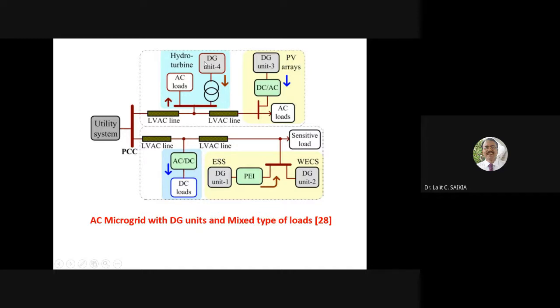Now one DG unit, say a hydro turbine—small hydro type power generation—can also be connected with this microgrid. This is connected via a transformer, since its output is different. We are not using a power electronic converter here, just a transformer. So you get the actual AC, and it is connected to the AC line.